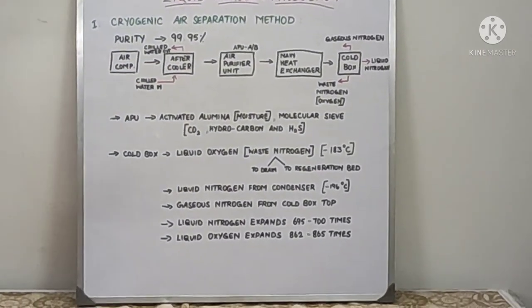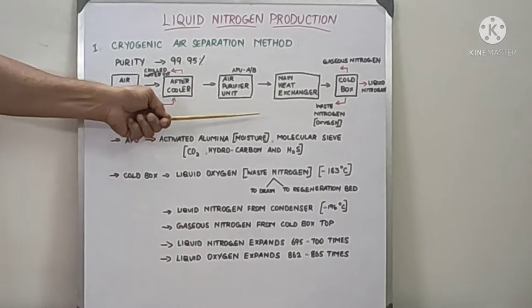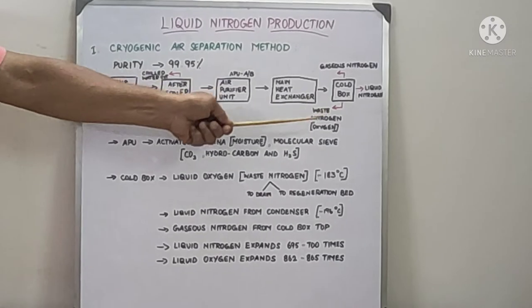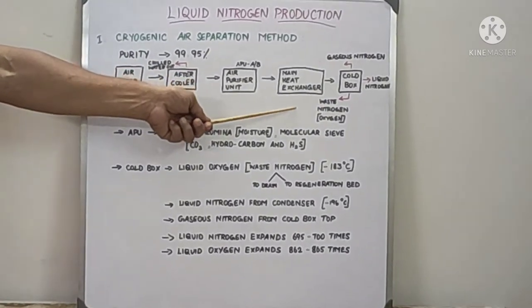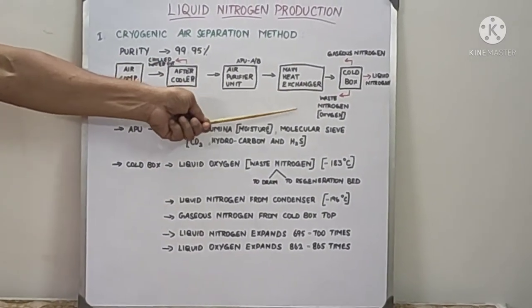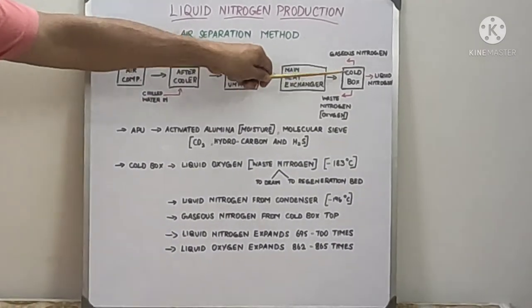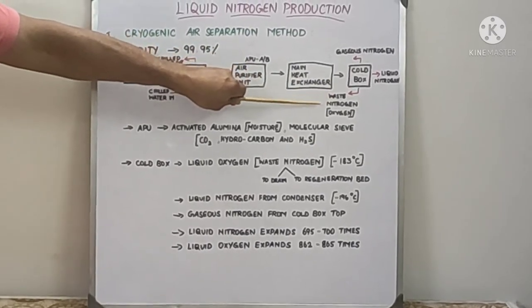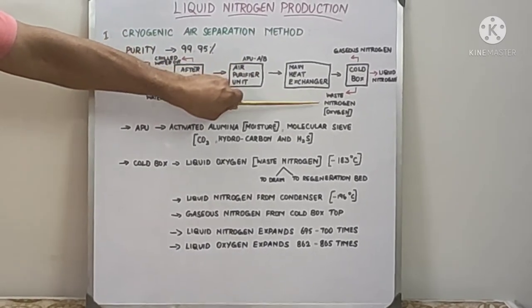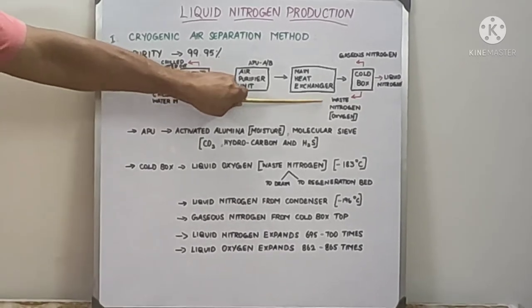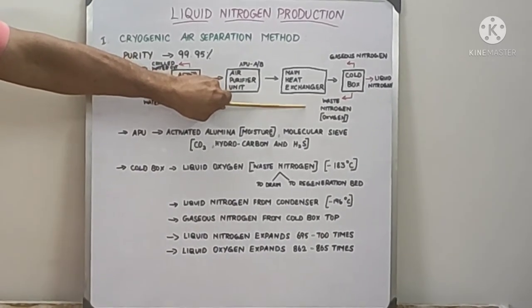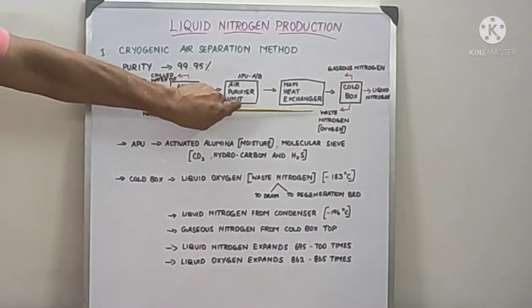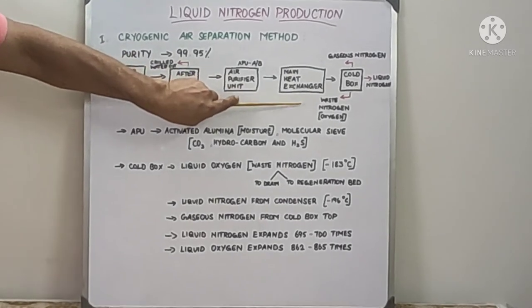You might have heard during the COVID-19 condition, many companies converted or increased production from liquid nitrogen to liquid oxygen. That is the medical oxygen system process. Instead of wasting this oxygen, they reduced the nitrogen production by increasing the condenser level at the bottom for collecting the waste oxygen and they drew the product without going to the vaporizer and collected in tankers.